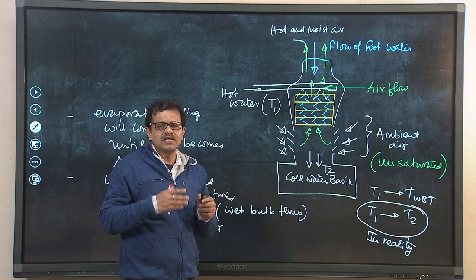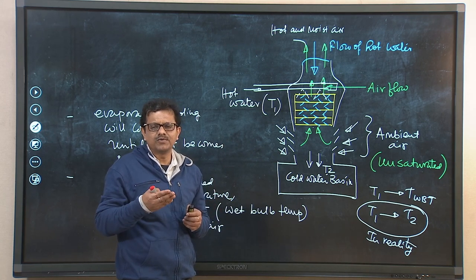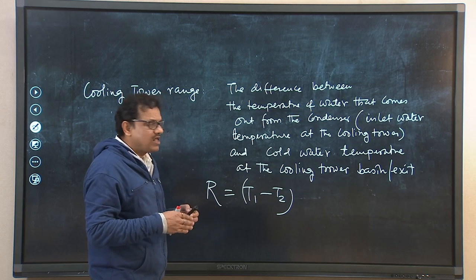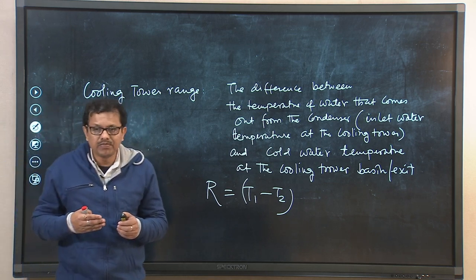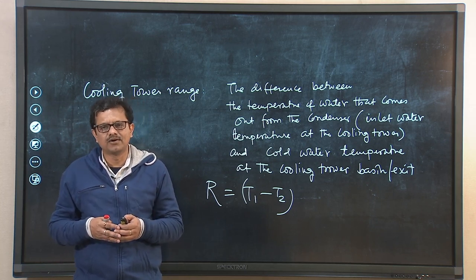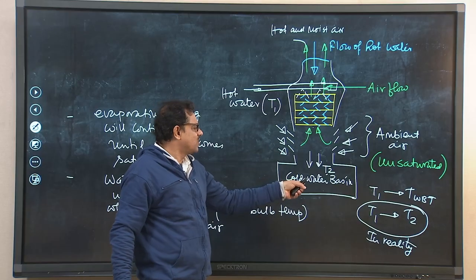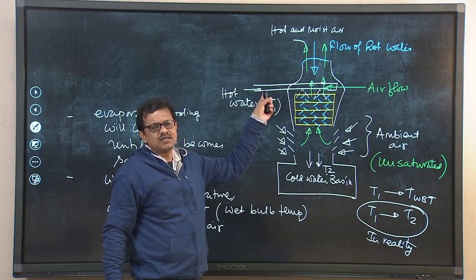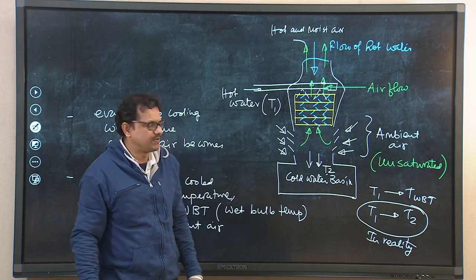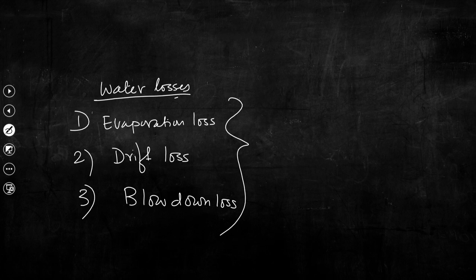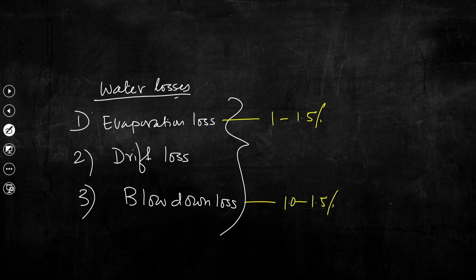There are three major losses: evaporation loss, drift loss, and blow down loss. All these losses need to be replenished by supplying makeup water. If makeup water is not supplied, the flow rate returning to the condenser will reduce, condenser efficiency will drop, and eventually total power plant efficiency will be affected. Typically, evaporation loss is 1 to 1.5 percent, blow down loss is also 1 to 1.5 percent, and drift loss is very minimal.